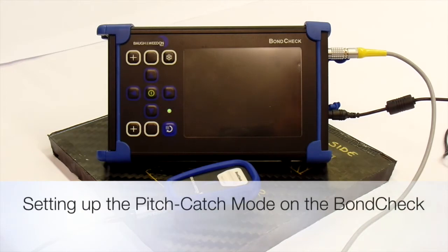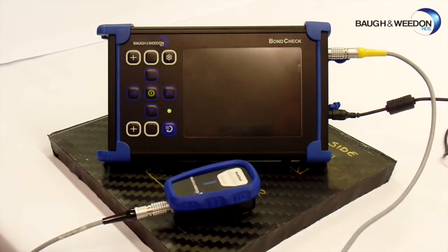We are now going to look at the BondCheck with pitch-catch mode and how to set it up on the instrument. Pitch-catch mode is used for honeycomb and foam core laminate structures.